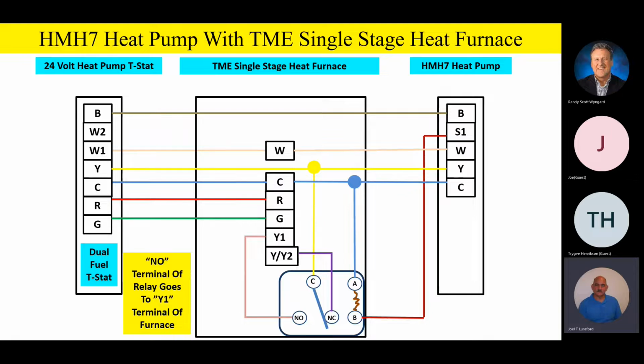So on our TME furnace, we're going to find that we've actually got hard physical screw terminals, but it's wired very much electrically just like we had on our previous slide with our air handler. Now, as we go in and take a look at it, we'll see that this single pole double throw relay, again, is a very, very simple relay with a 24-volt coil, and we're just hooking it up real simply like we did before. Any questions or comments so far before we start looking at some other features with a two-stage furnace and a couple other things? Any questions or comments?